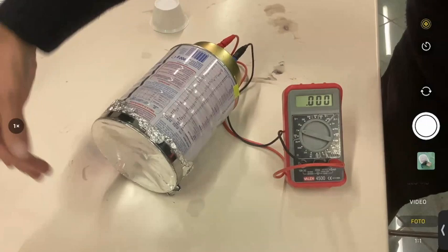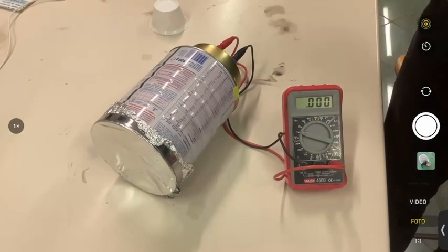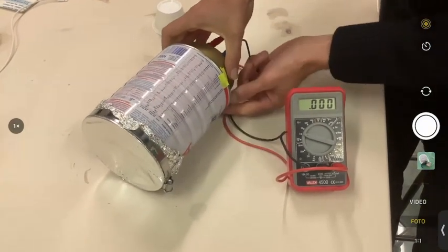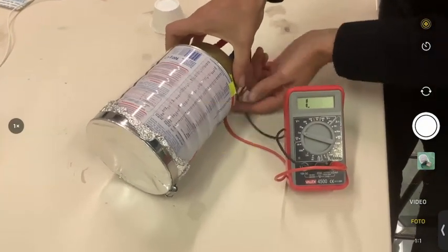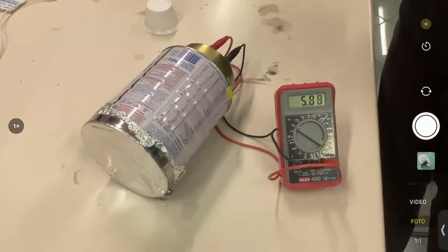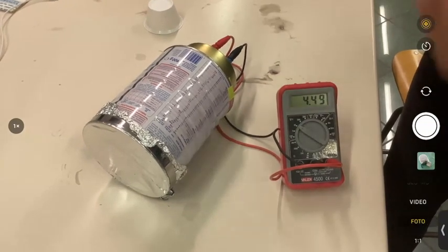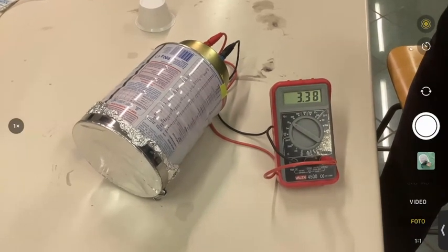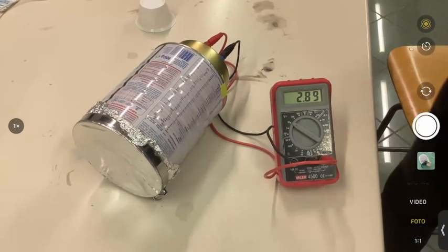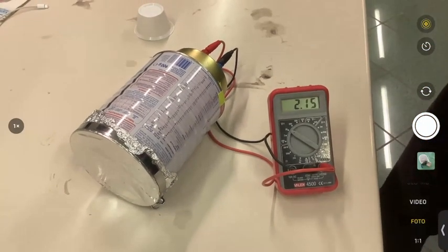So, how does it work? If I put something in front of the chamber, it will detect some radioactive particles. First of all, I switch on the ion chamber. You can see that in the first step, the ion chamber has to reach a stable condition of less than 1 volt.